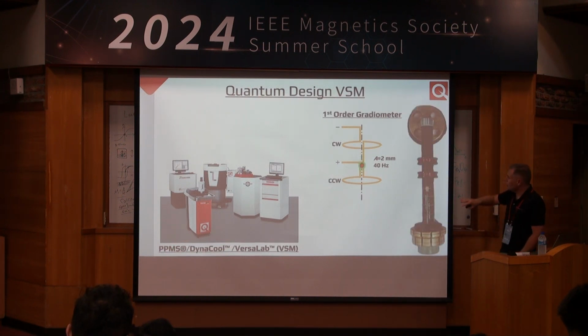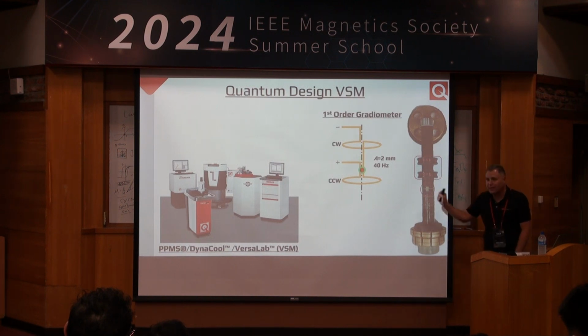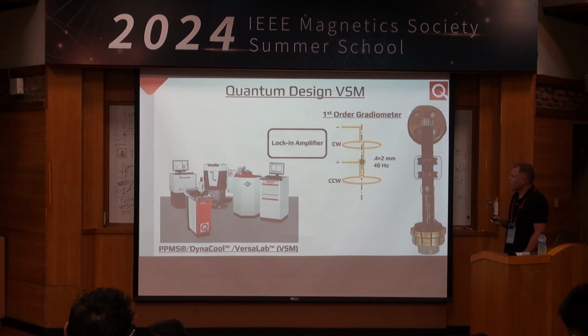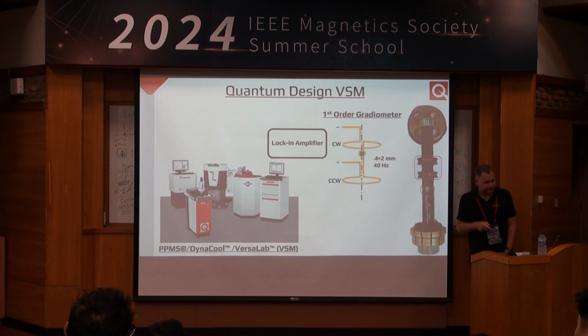We actually take a look at our coil set. We take the protective covering off of it. What do we see? Here's that first-order gradiometer. This is just standard copper wire here. Nothing too fancy going on here. This here is a calibrated Cernox thermometer, so we know as close as possible to the sample what the temperature is. It's very critical in our type of systems. And of course, there's a lock-in amplifier which exists in the electronics bay here. So again, pretty basic stuff.